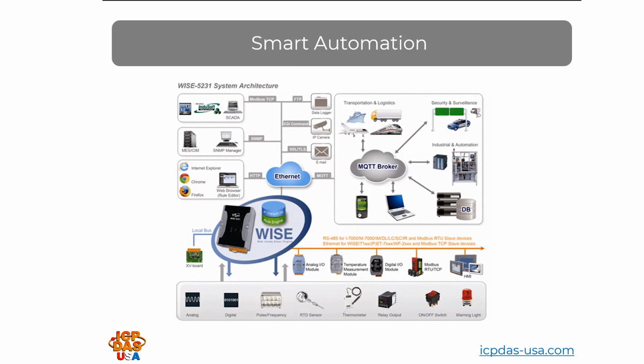Our WISE 5800 series smart automation controllers are configurable through a web page, and they're being used for monitoring and control in mechatronics applications. WISE stands for Web Inside Smart Engine, and it supports Modbus TCP communication. It triggers outputs based on inputs, sends email alarms based on schedules or conditions. It shows the system status through a web page. They integrate easily with I/O modules and sensors on the field side, support various IoT protocols, and integrate easily with SCADA systems. They allow for real-time I/O logic control, and they also log data.